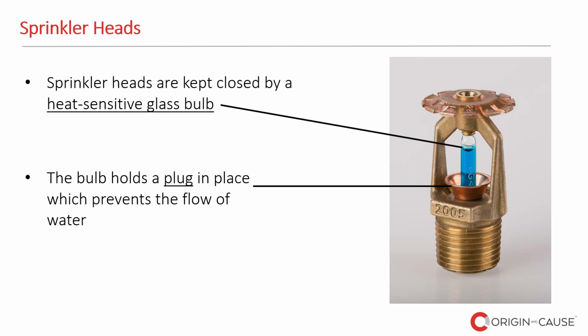So the main parts of a sprinkler head are usually brass material, and they have either a heat-sensitive glass bulb, or in some cases a soldered fusible link. And what it does is it holds a cap in place. Once that glass bulb bursts because of the temperature, then water starts to flow.